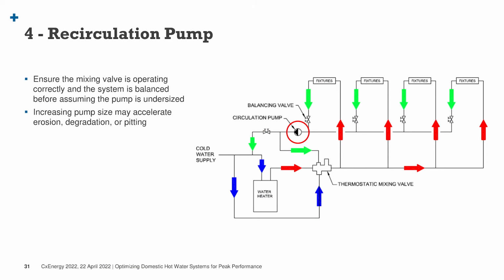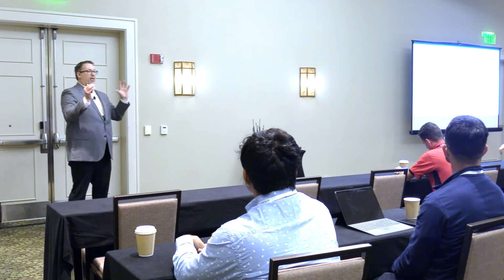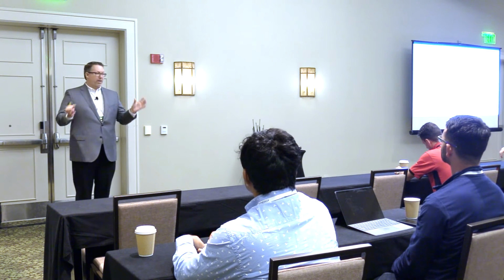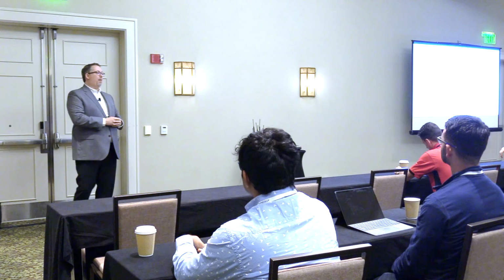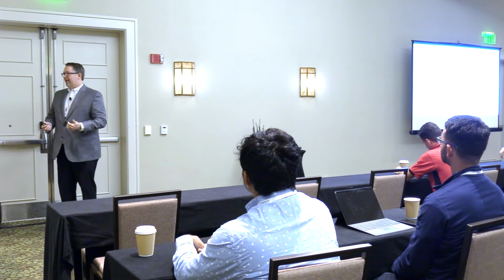And then as we move to the end of the system, that's when we look at the recirc pump. So once we've already eliminated the water heater as a problem, the mixing valve as a problem, confirmed that the system is balanced, then look at the recirculation pump and see if it's properly sized, see if there's some issues there. Because a lot of times what we kind of default to is, after we evaluate the water heater, say there's not a problem, we say, well, the pump is a problem. So then we go back and we try to increase the size of the pump. That can create some other issues.